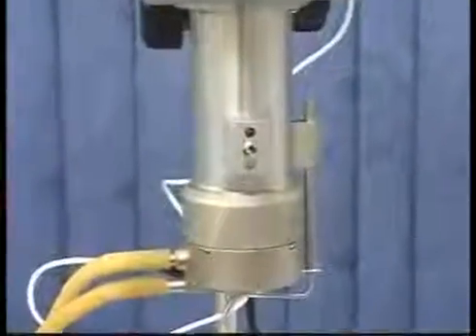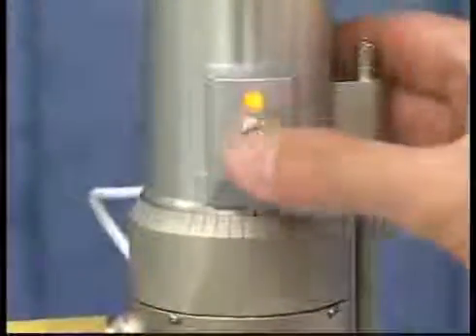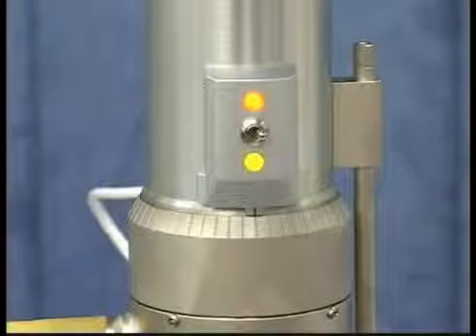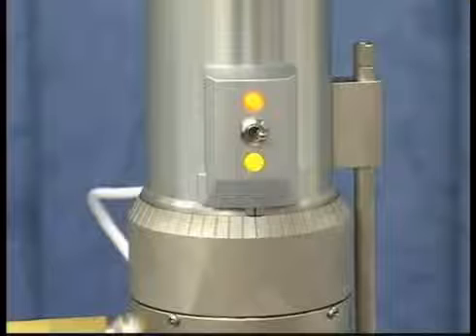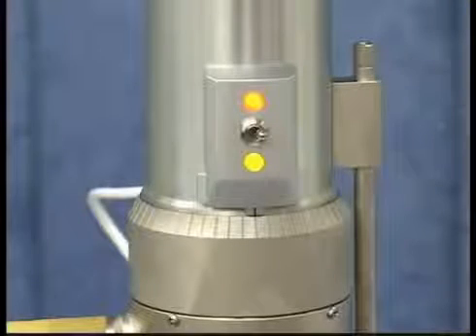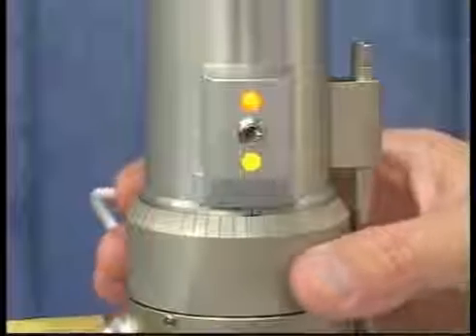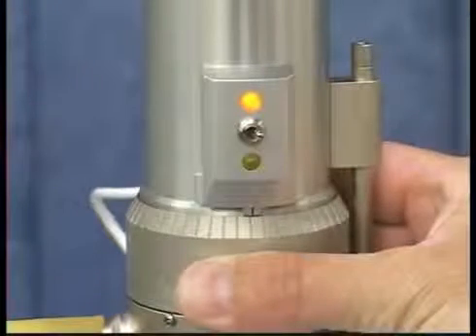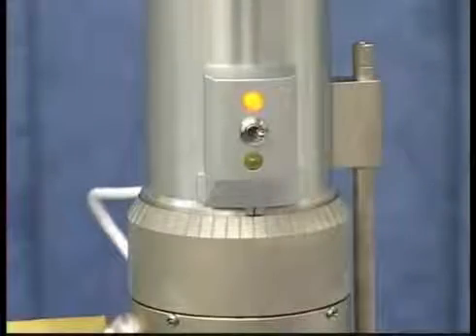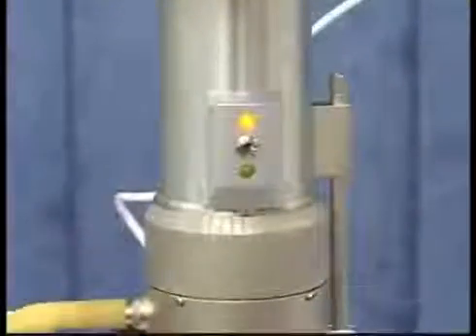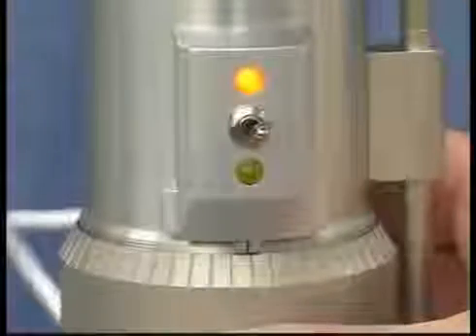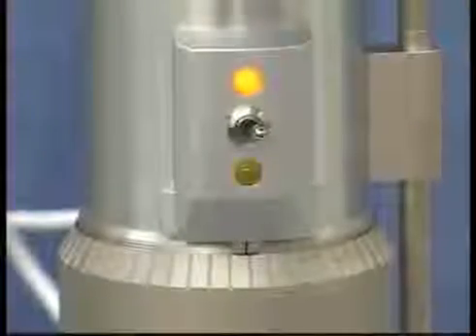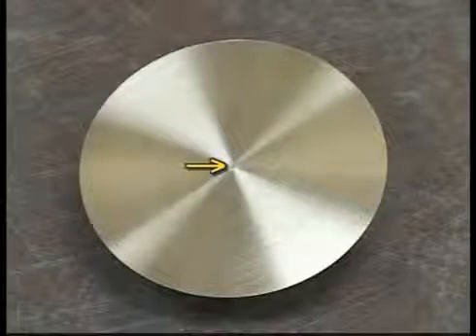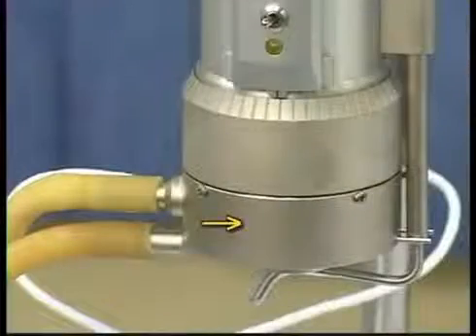Brookfield's cone plate instruments use an electronic gap setting feature. Move the toggle switch to the right and you will see the red light illuminated. If the yellow contact light is illuminated, slowly turn the micrometer ring clockwise as you look down on the instrument until the yellow light is no longer illuminated. If the yellow contact light is not illuminated, slowly turn the micrometer ring counterclockwise until the yellow light first turns on or begins to flicker. This is the hit point, where the pin in the nose of the cone spindle is touching the plate, which is part of the cup.